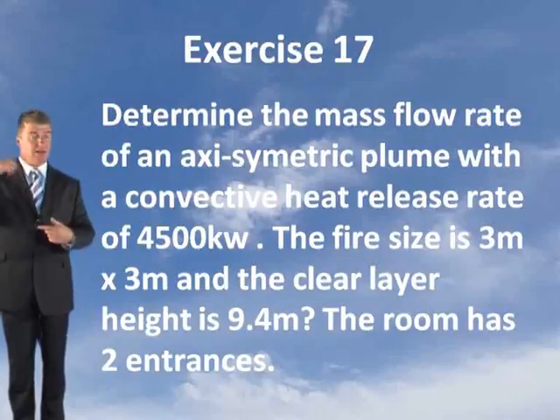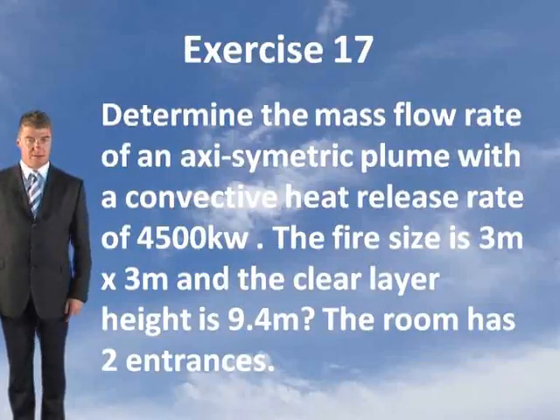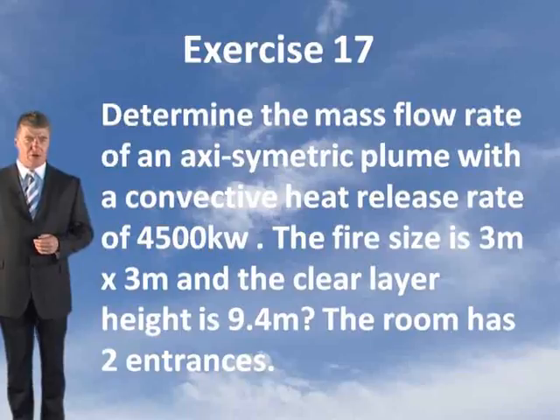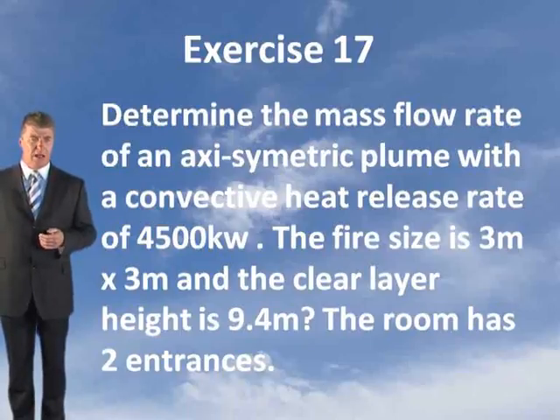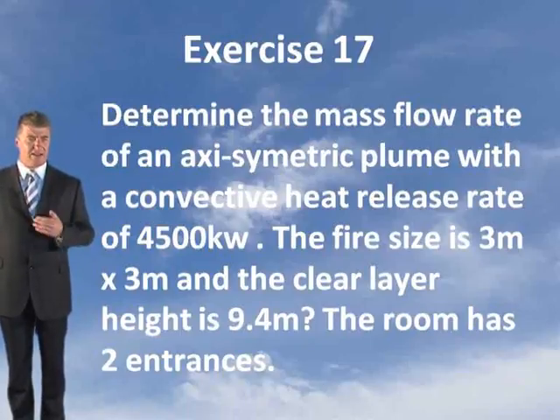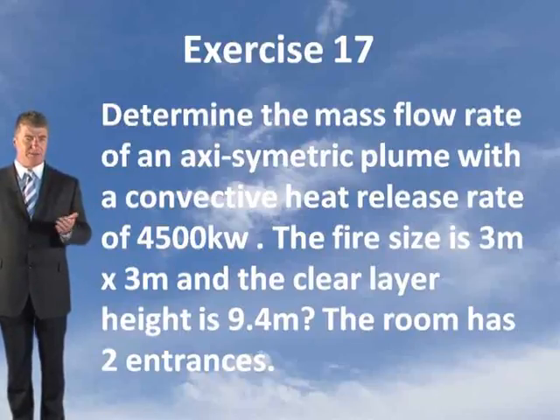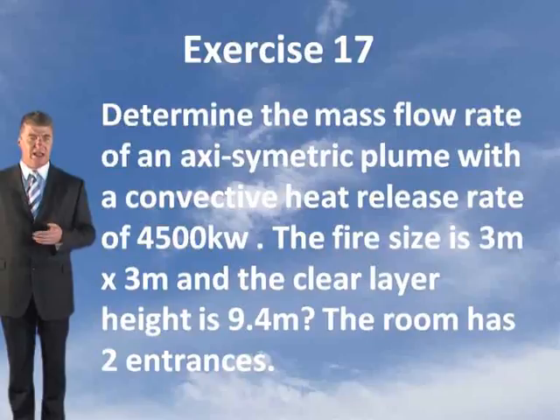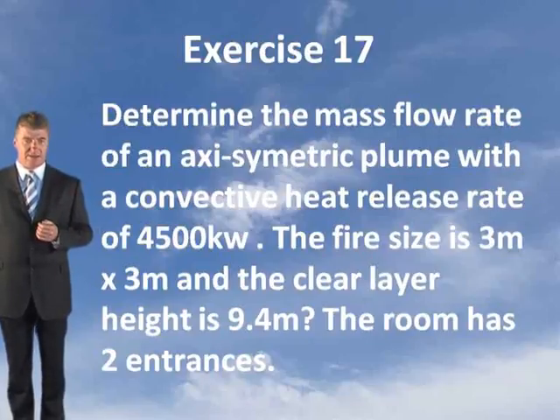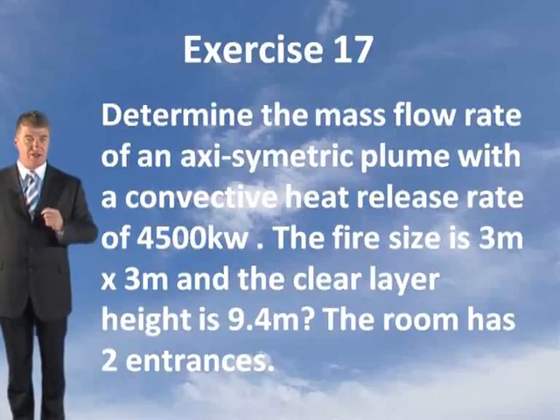In this exercise 17, determine the mass flow rate of an axisymmetric plume with a convective heat release rate of 4500 kilowatts. The fire size is 3 metres by 3 metres, the clear layer height is 9.4 metres, and the room has two entrances.